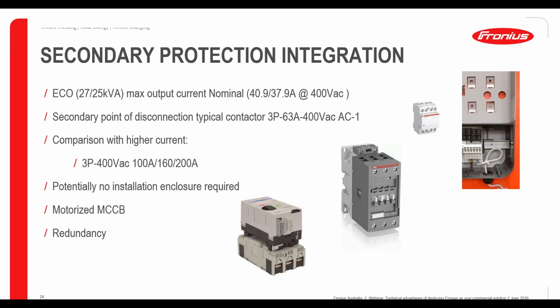Also, an important thing: as the size gets bigger, contactors grow and motorized circuit breakers kick in, then the requirements for the enclosures change. Typically they require back plates, bigger enclosures, and more labor as bigger cables are involved. Also, aggregating the system to one disconnection point reduces the redundancy level of the system. So if a system device fails, it may drop the whole system, instead of if you had multiple disconnection points.